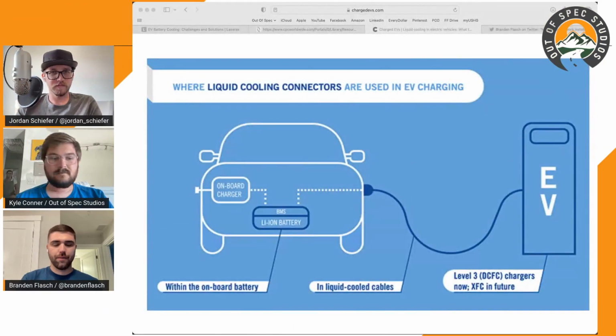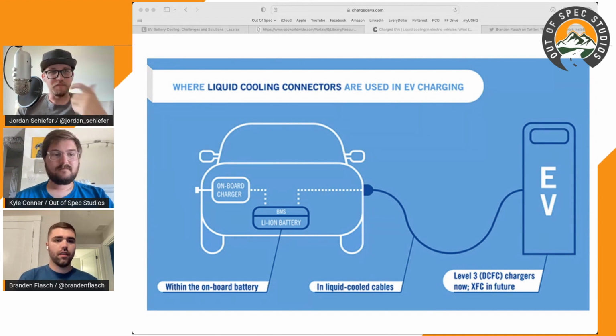And the reason that you have to use a dielectric fluid is that it's actually running not only inside the cable, but it's also running inside the charging handle itself, because anytime you have a connection point, that's going to be essentially a hot spot. And in the charging handle, you have a connection to the vehicle. You also have connections between the wires themselves or conductors, and then the actual charging contacts that are in that externally accessible plug that goes to the vehicle. So it's very complicated.